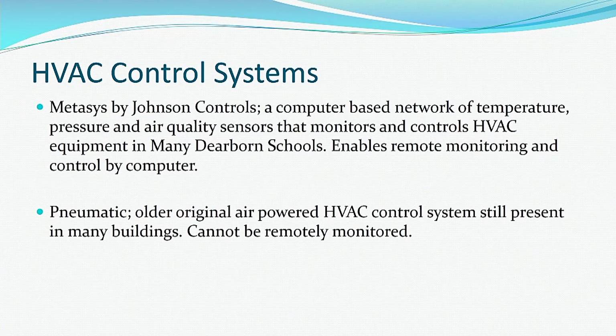HVAC control systems. We're fortunate here in the district to have something called Metasys. It's a product by Johnson Controls, and it's a computer-based network of temperature, pressure, and air quality sensors, control valves, and damper actuators that monitor and control the HVAC equipment throughout the district remotely. We can control that with our computers. Not the entire district, though. Some portion of the district still has pneumatic, older, original air-powered HVAC systems, the air-operated thermostats you sometimes hear about. Those cannot be remotely monitored.